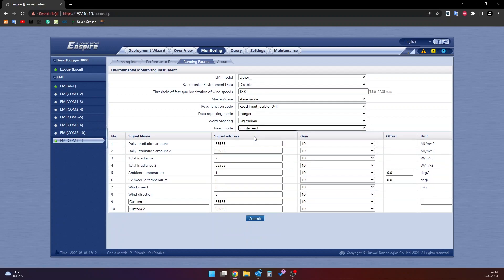At the bottom of the page, there is the sensor configuration section. In order for the sensors to be displayed on the monitoring screen, the signal address section must be completed in accordance with the sensor registration addresses. For sensors that are not connected or that you do not wish to be displayed on the monitoring screen, the code 65535 must be entered instead of the registration address. The spaces indicated as custom at the bottom are used to define another sensor which is not on the screen. The register addresses of the sensors that are connected and whose data we want to check are entered as follows.